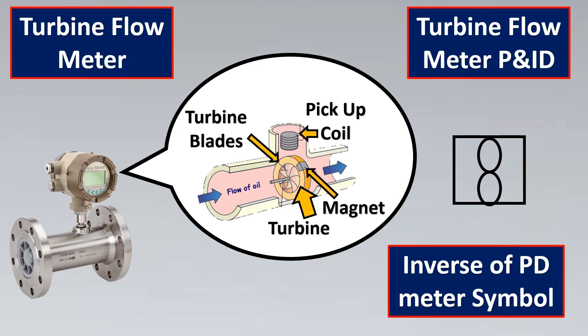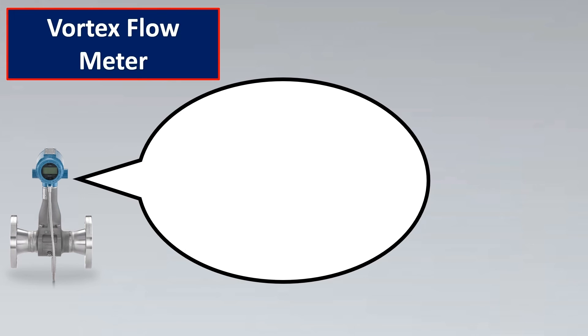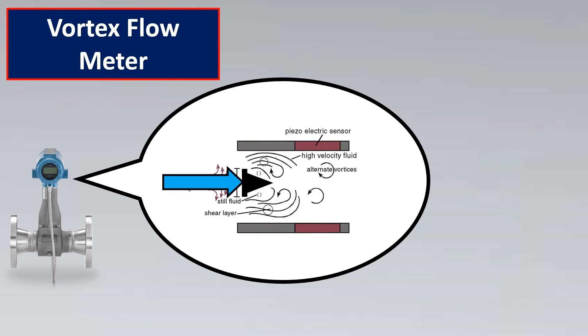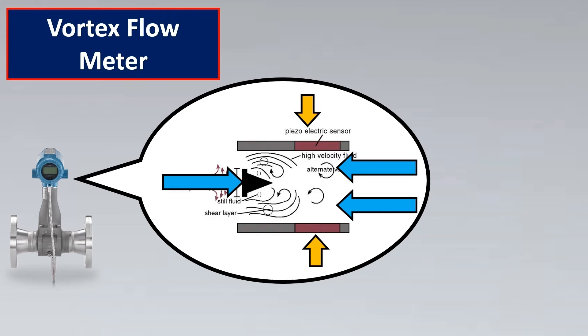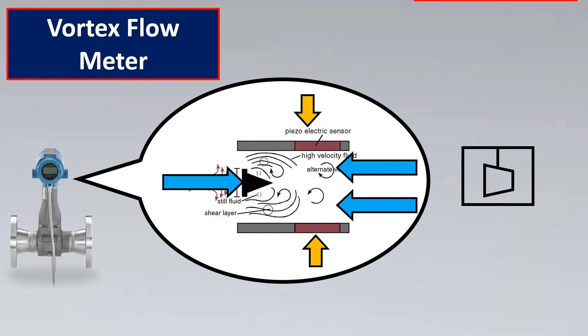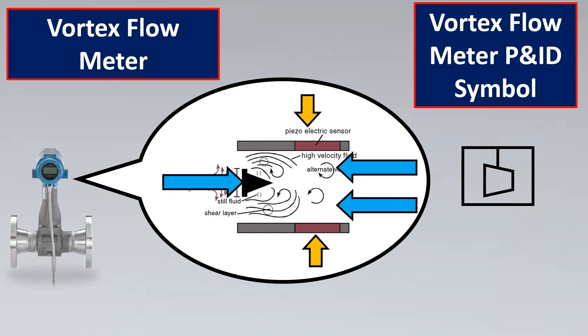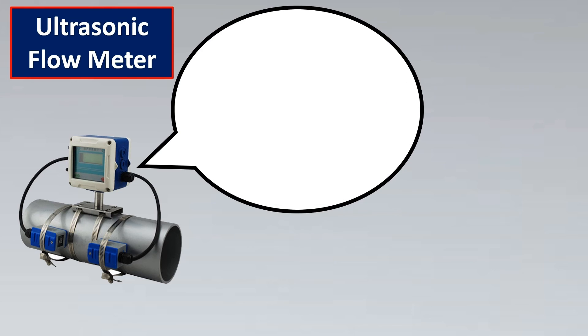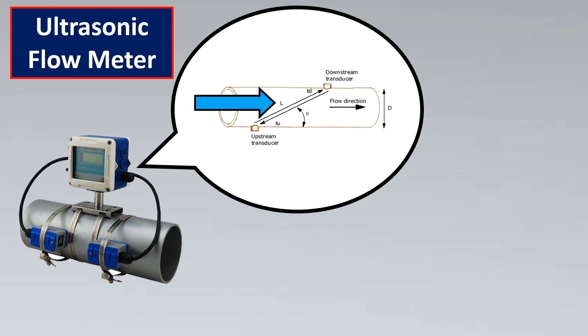For the vortex flow meter, a bluff body is placed in between the flow path, creating alternating vortices. The higher the flow, the higher the frequency of vortices, which are detected by a piezoelectric crystal. The most important element — the bluff body — has been used for the P&ID symbol along with the pipe body. This is your vortex flow meter P&ID symbol.